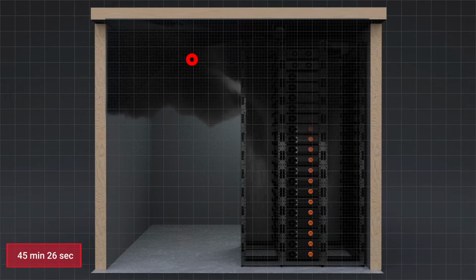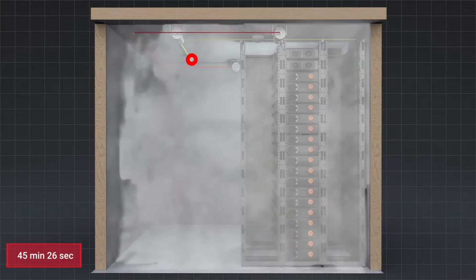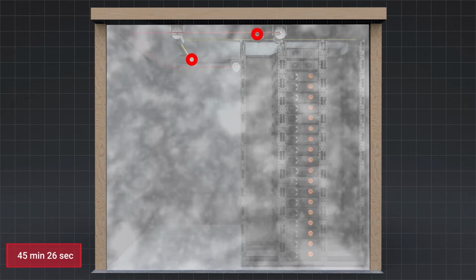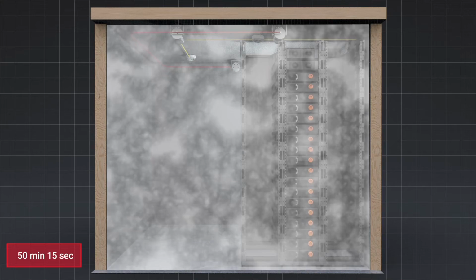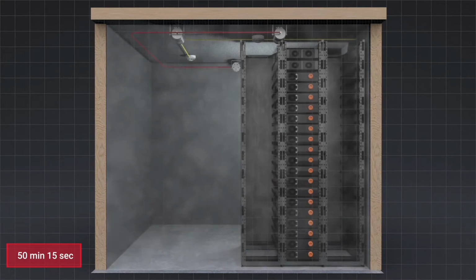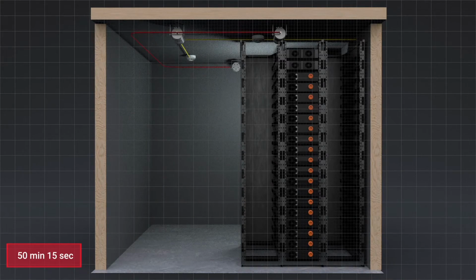At 45 minutes and 26 seconds, the StatX system was activated and the aerosol was released for 30 seconds, inhibiting propagation of thermal runaway to adjacent battery racks. At 50 minutes and 15 seconds, the enclosure was ventilated and the test was complete.